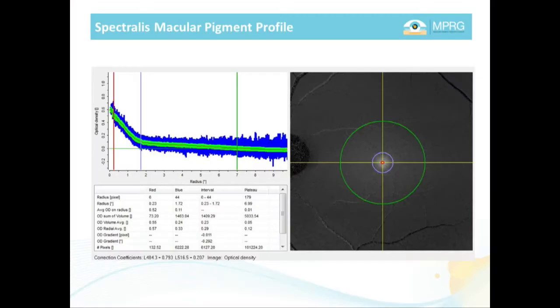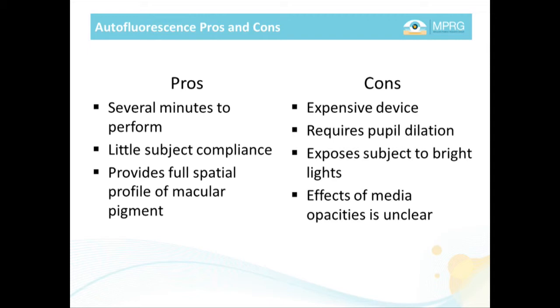This is what the output of that device looks like — you get a full spatial profile across the retina. The pros of autofluorescence: it only takes several minutes to perform, requires little subject compliance, and provides a full spatial profile. The cons: the device is very expensive, requires pupil dilation, subjects are exposed to bright levels of light, and the effects of ocular media are unclear. However, we're thinking about starting a research project to investigate the effects of cataracts on the Spectralis autofluorescence method.